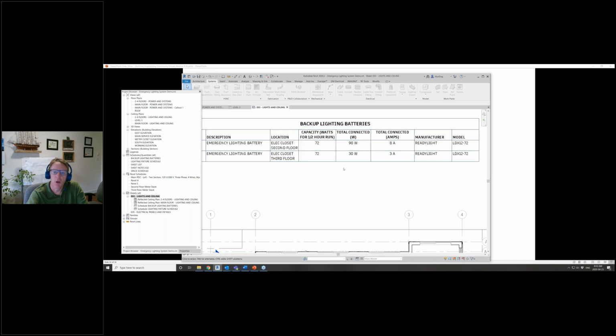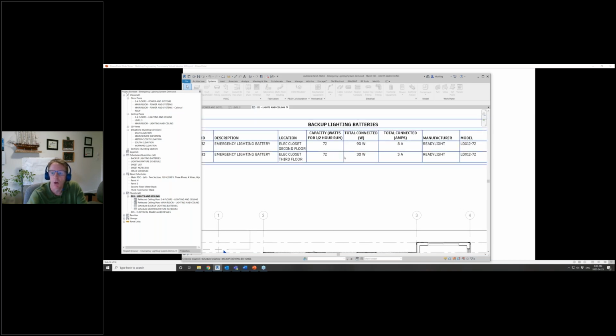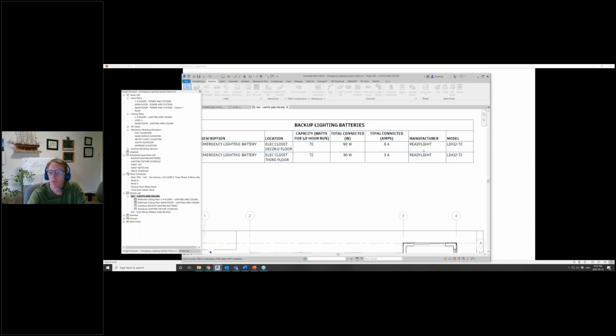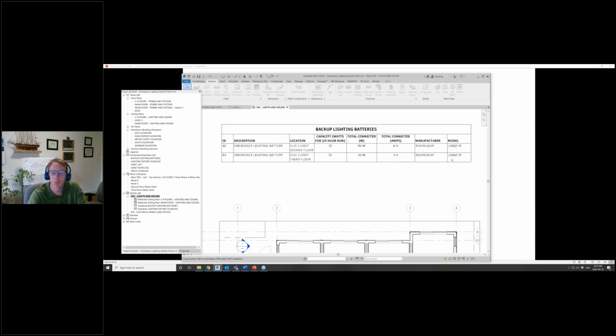So from this, we can tell that the wattage is less than the half-hour runtime rating, so we know that this battery unit is adequate for its job. The battery should last at least 1 hour runtime, so we meet our code. Also, we have the part number of the manufacturer and the part number of the battery. Good stuff to give your electrical contractor.